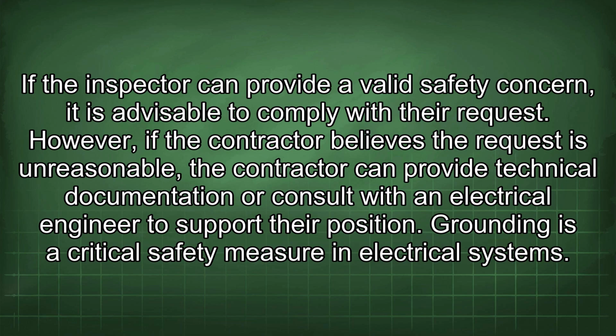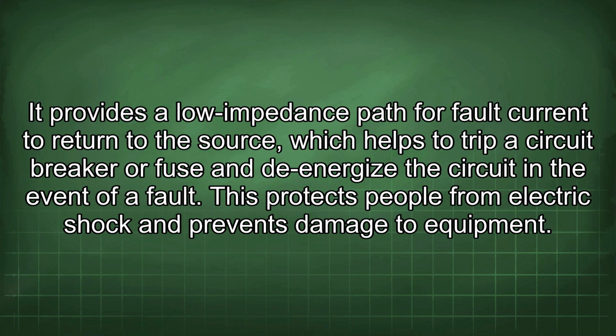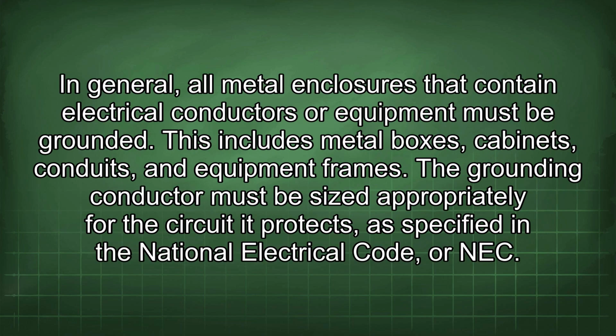Grounding is a critical safety measure in electrical systems. It provides a low impedance path for fault current to return to the source, which helps to trip a circuit breaker or fuse and de-energize the circuit in the event of a fault. This protects people from electric shock and prevents damage to equipment. In general, all metal enclosures that contain electrical conductors or equipment must be grounded. This includes metal boxes, cabinets, conduits, and equipment frames.